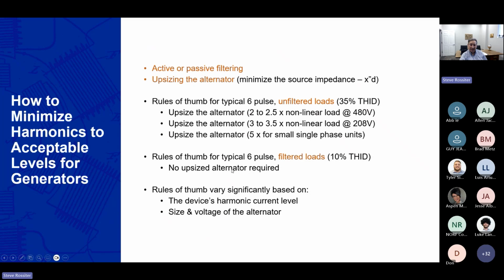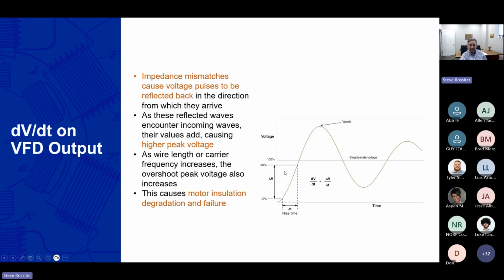Generators, I'll just mention, because when you have any variable frequency drive on a generator, you need to be concerned about the alternator. There are methods of doing calculations to make sure that you don't have too much harmonics, but typically if you get below 10% THD, you're getting in the range where the alternator won't be negatively affected. So now I'd like to spend the last maybe a couple of minutes anyway on the output of the drive.